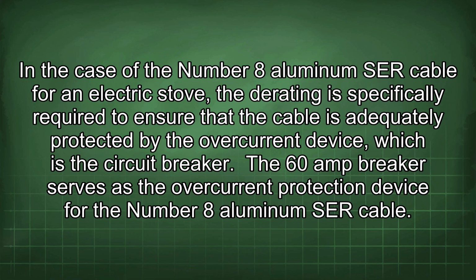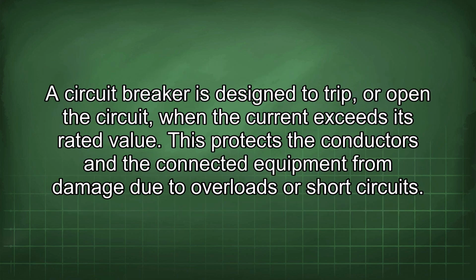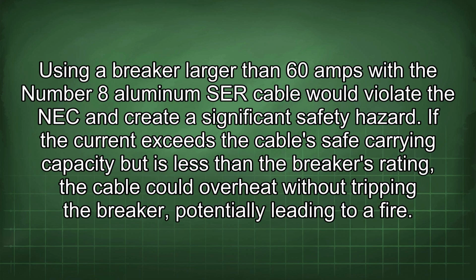The 60 amp breaker serves as the overcurrent protection device for the number 8 aluminum SER cable. A circuit breaker is designed to trip or open the circuit when the current exceeds its rated value. This protects the conductors and the connected equipment from damage due to overloads or short circuits. Using a breaker larger than 60 amps with the number 8 aluminum SER cable would violate the NEC and create a significant safety hazard. If the current exceeds the cable's safe carrying capacity but is less than the breaker's rating, the cable could overheat without tripping the breaker, potentially leading to a fire.